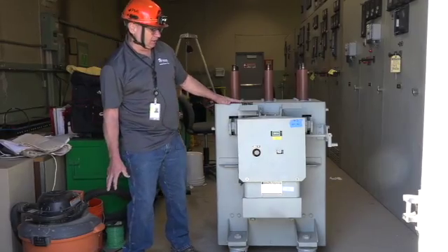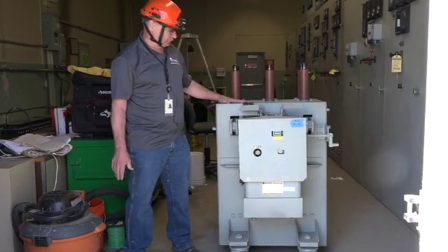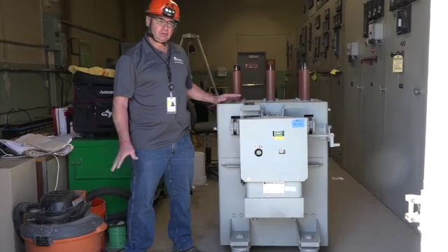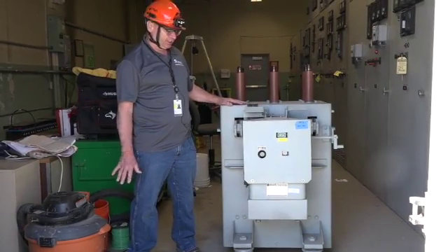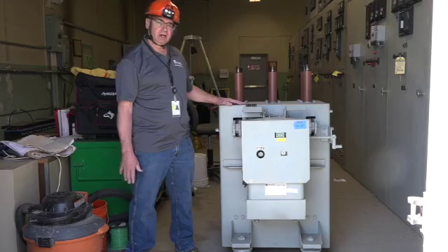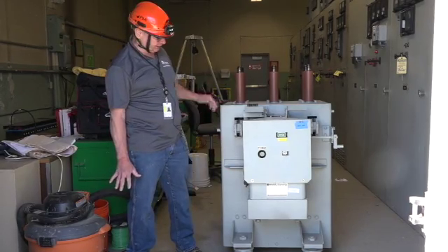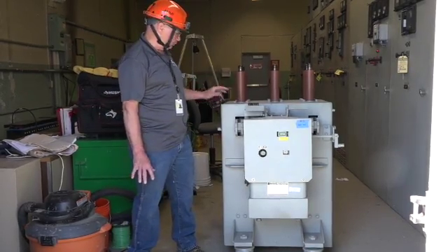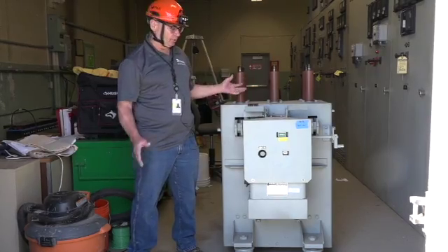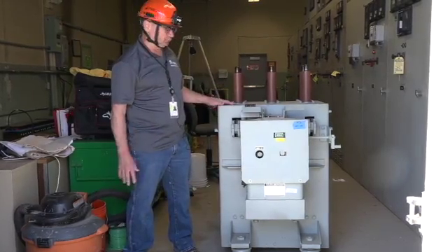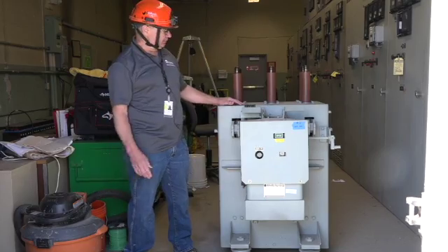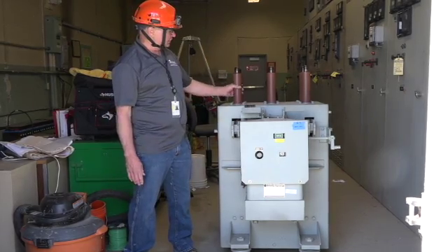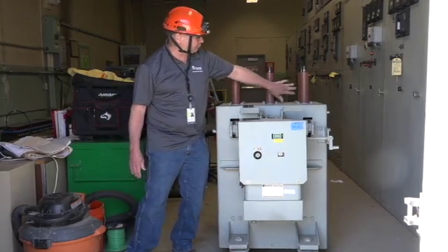This equipment here is a newer style circuit breaker, a little bit newer style. It's called a Magne-Blast circuit breaker. This one, there's no oil in it. It's all done with arc chutes for when the breaker opens and closes to extinguish the medium voltage arc. But you can see it has the same contact bushings.